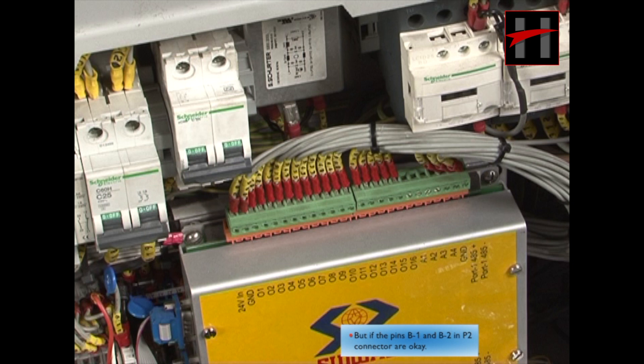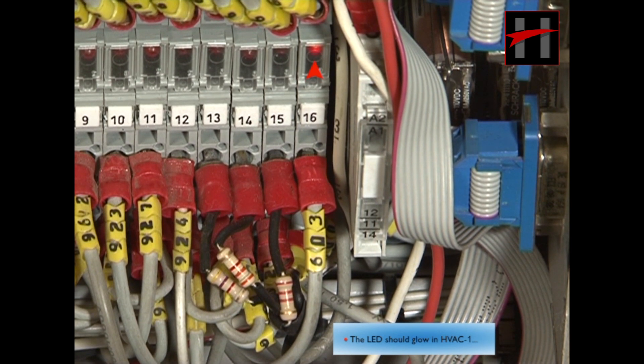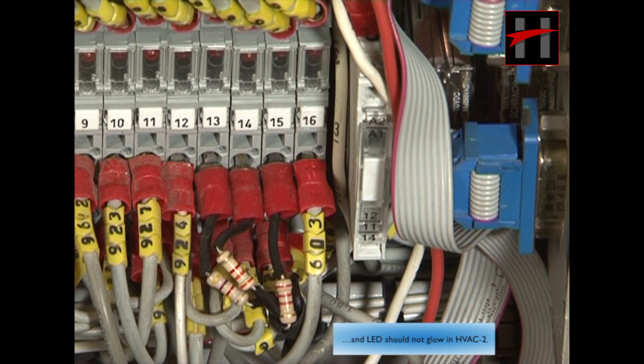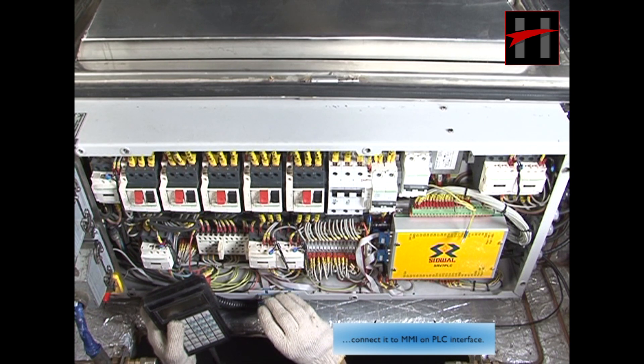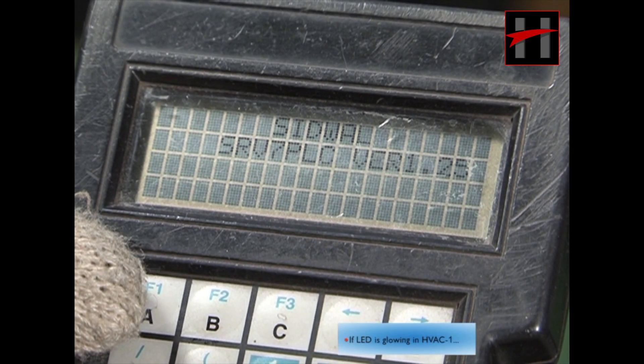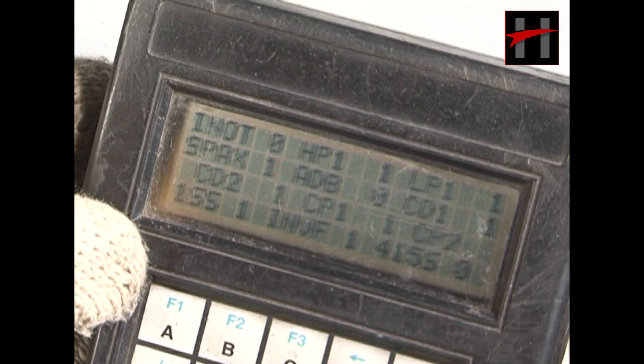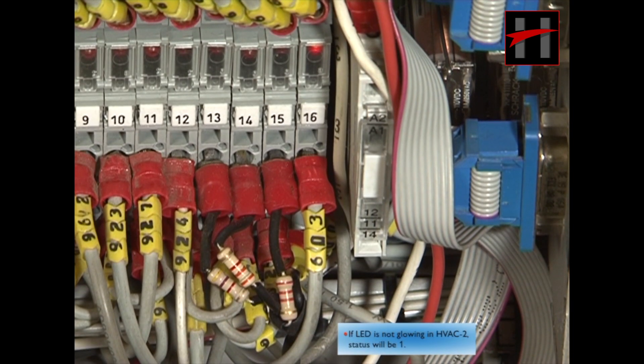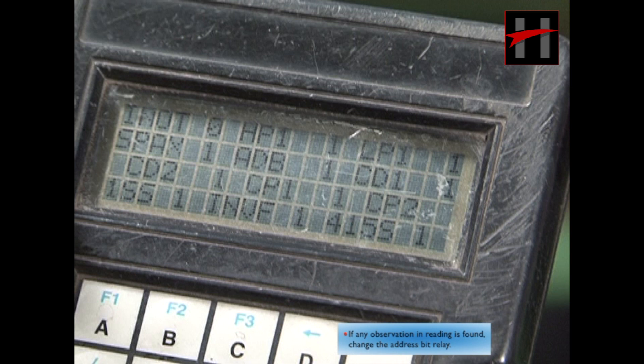But if pins B1 and B2 in the P2 connector are okay, then check the address bit relay with its LED. The LED should glow in HVAC 1 and should not glow in HVAC 2. If the address bit relay with LED is okay and HVAC is still not communicating, connect it to the MMI or PLC interface. If the LED is glowing in HVAC 1, the status of the address bit will be 0 on MMI. If the LED is not glowing in HVAC 2, the status will be 1. If any anomaly in reading is found, change the address bit relay.